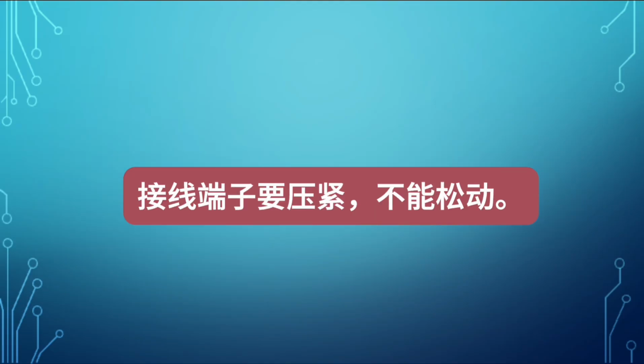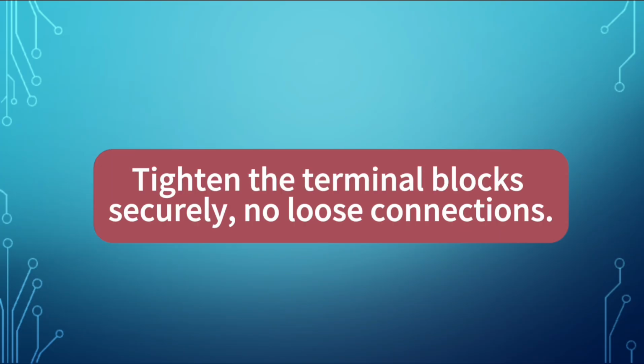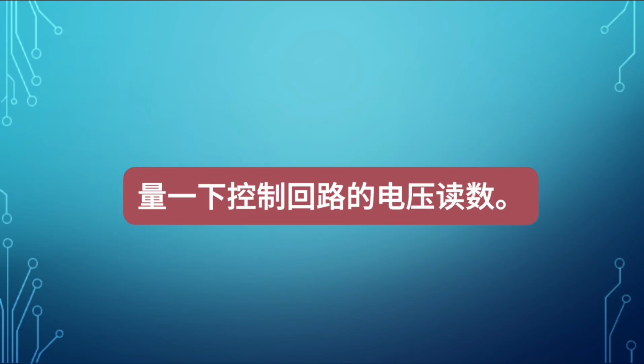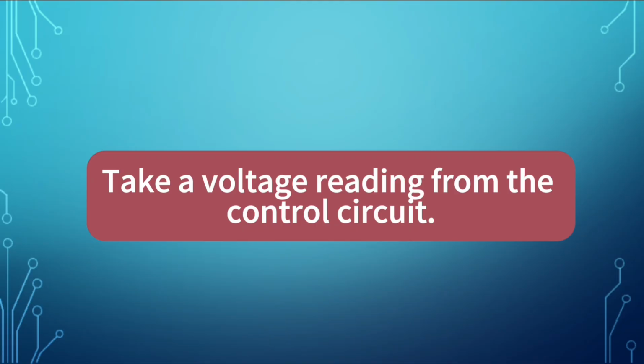Tighten the terminal blocks securely. No loose connections. Take a voltage reading from the control circuit.